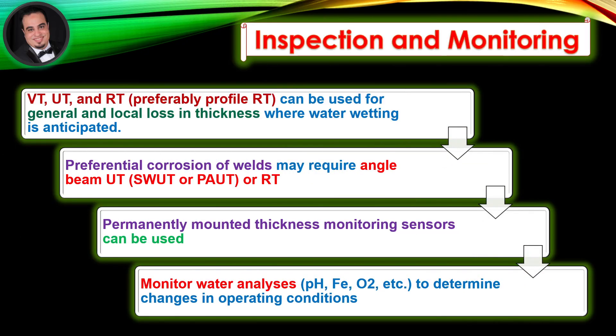Inspection and monitoring: VT, UT, and RT — preferably profile RT — can be used for general and local loss in thickness where water wetting is anticipated. Preferential corrosion of welds may require angle beam UT, SWUT, PAUT, or RT. Permanently mounted thickness monitoring sensors can be used. Monitor water analyses: pH, Fe, O2, etc., to determine changes in operating conditions.